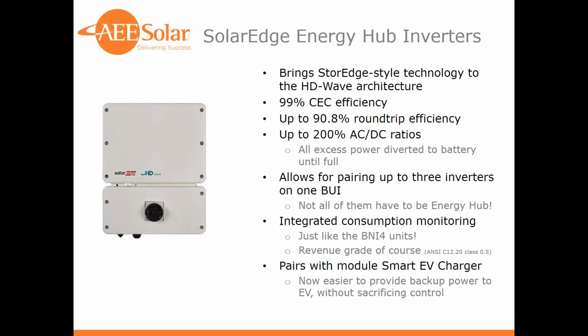Typically the way this would work before, if you were absolutely dead set on backing up your EV charger, you would wire that circuit into your backup loads panel, and then you're really at the mercy of the car's charging profile and the other loads, risking overpowering your inverter in a backup situation.